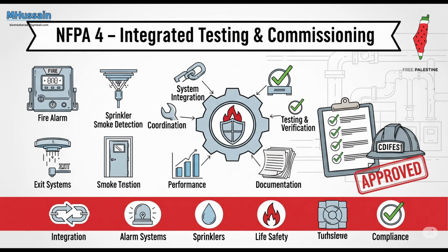Absolutely. This standard applies to integrated passive systems, things like fire-rated walls and doors that contain a fire, and active systems like sprinklers and alarms that actively respond. It's specifically designed to test how all these different pieces communicate and interact. Not just checking if the sprinkler head works on its own. Exactly. It's about the chain reaction. Does the sprinkler activating correctly trigger the alarm? And does the alarm correctly trigger, say, elevator recall or smoke management systems?